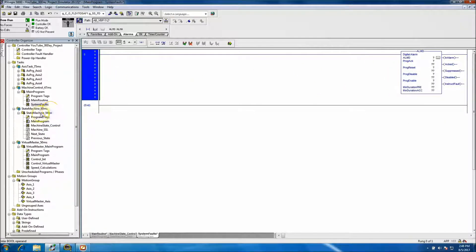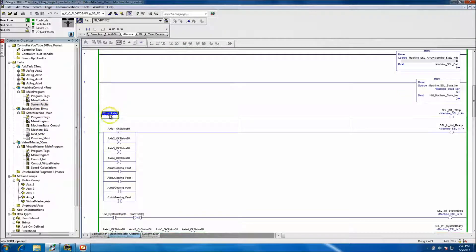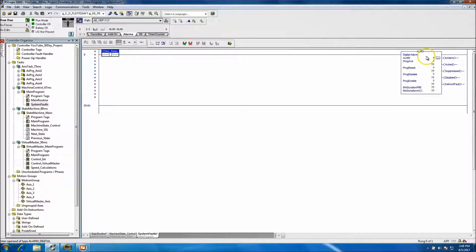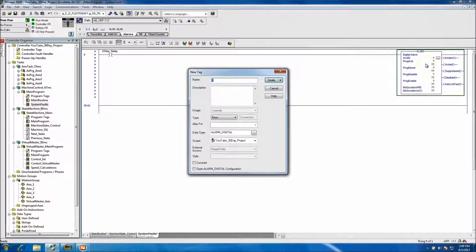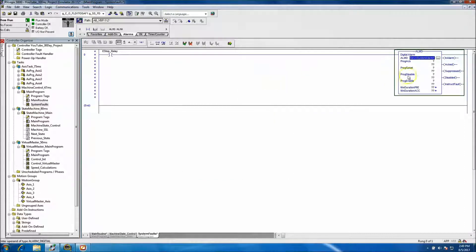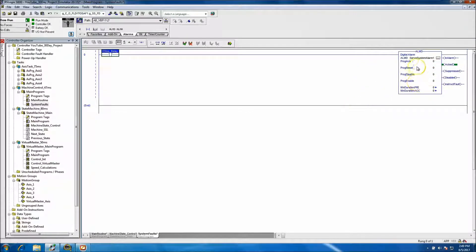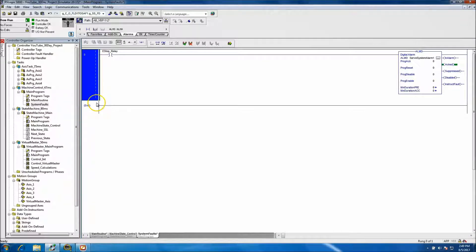Without further ado, we'll put a couple of ALMDs in. We want to grab the e-stop relay bit — the first bit we have — jump back over, paste that in, and basically name this instruction. We'll call it 'Servo System Alarm 1,' and they would just keep cascading down from there. I'm not going to add any control logic for acknowledging from this side; I'll let that happen via the HMI.